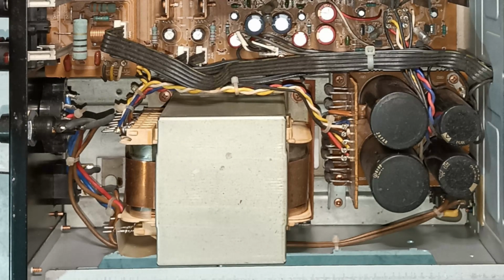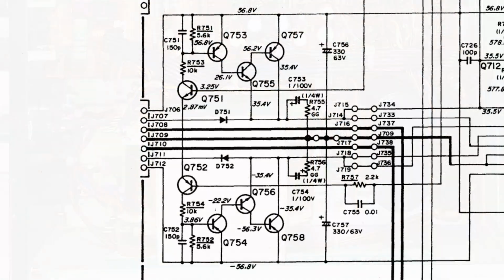Please notice that inside the cabinet, the internal power supply is not isolated, nor shielded, and servicing it requires the same care for safety that one should have for servicing a vacuum tube radio. Moreover, the main board is powered with different DC lines, two of which provide plus 56 and minus 56 volts, and these are already dangerous voltages.